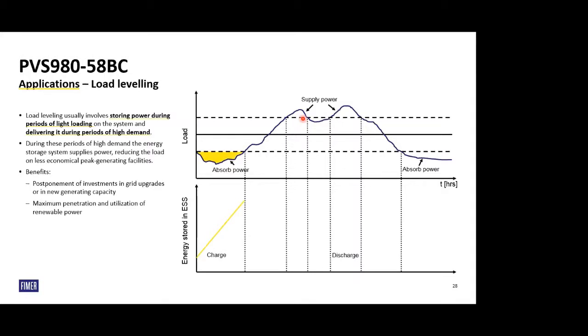Whenever the load goes below a set point, we charge the batteries. Whenever it is in between these two, we hold the charge. Then whenever it crosses a set point, we discharge the batteries in order to shave the peak, so that your grid is not loaded. So the grid will still see the same load. Whenever it is below, we hold, and whenever it exceeds, we discharge the batteries. Whenever it is in between the set points we hold, and whenever it goes lower, we charge and get ready for the next peak to address.